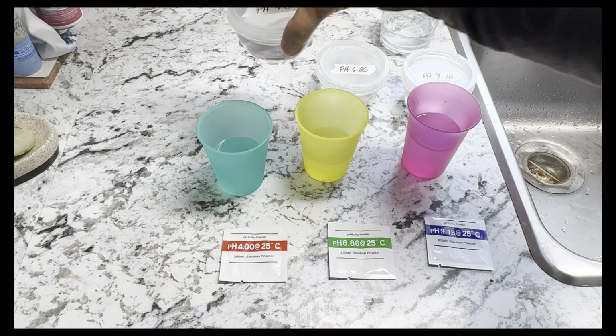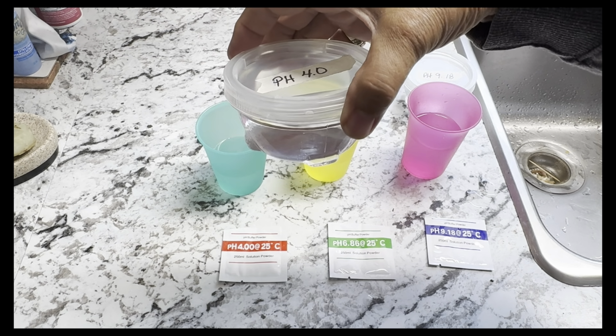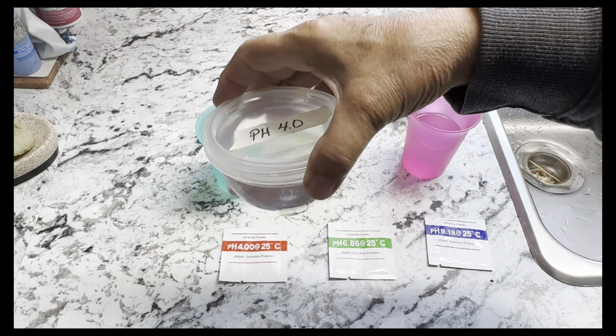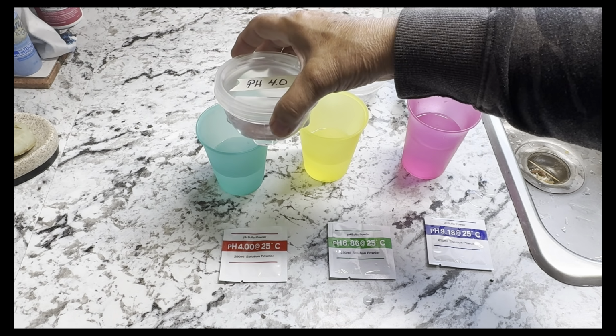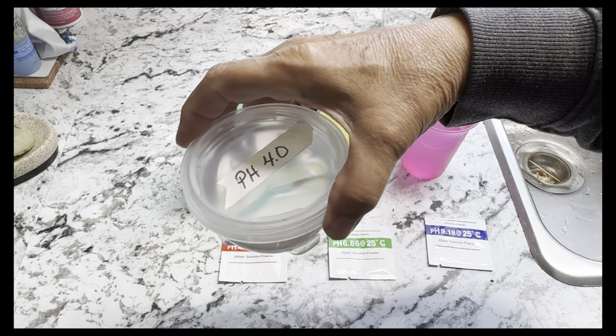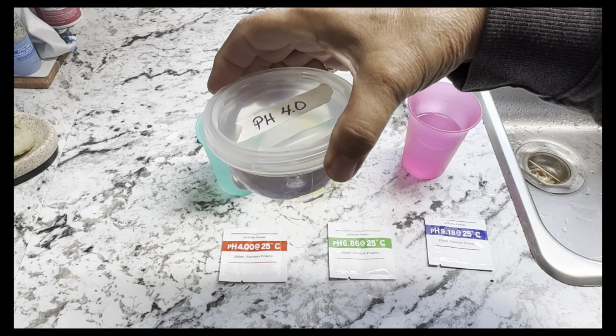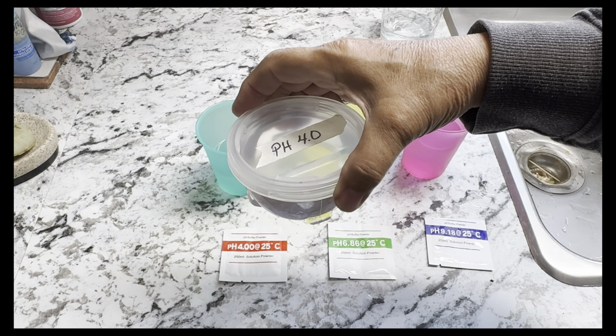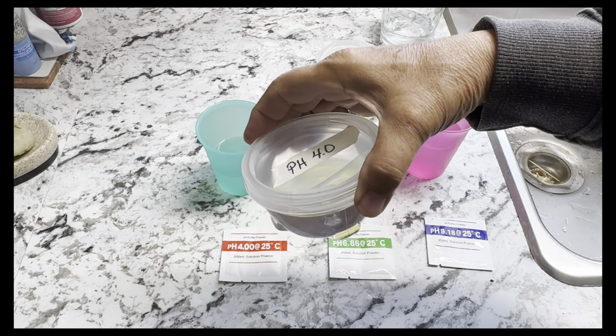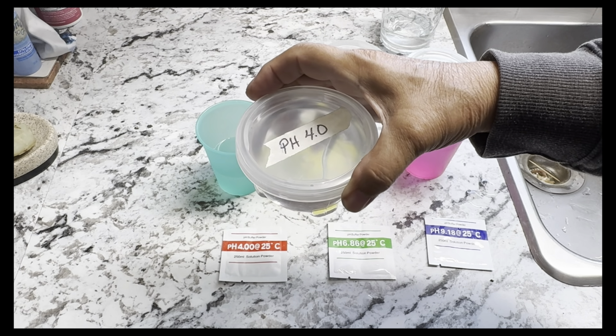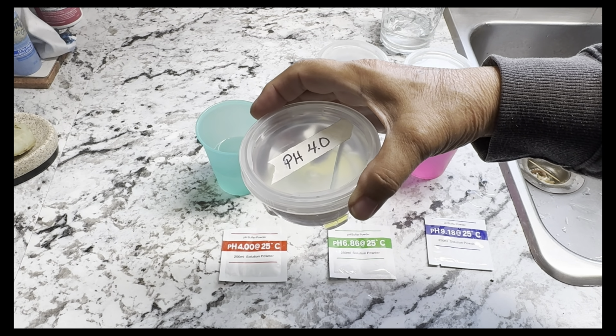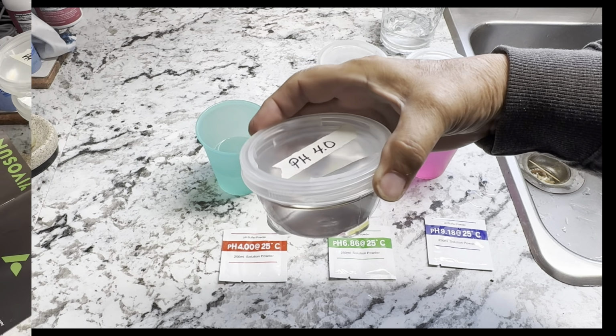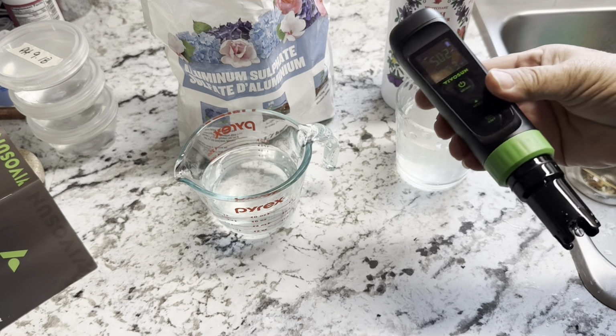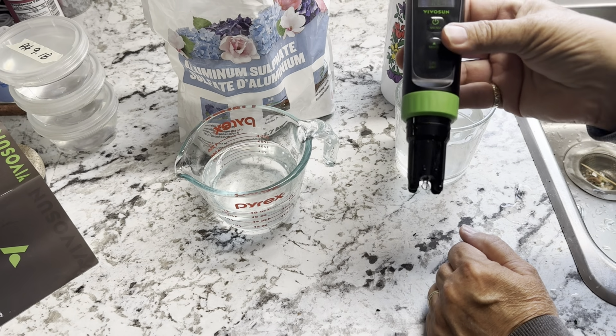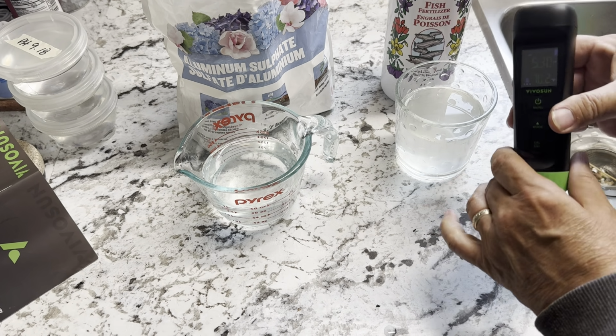So you're going to be mixing up a 250 milliliter solution from each of these packages. You don't have to use it all at once. I only put about 50 mils in this cup. You can store the excess away on the shelf out of direct sunlight. As long as it stays cool, you should be able to use this again to recalibrate over the next 3 to 6 months. So once you got your meter all calibrated, you're ready to test pH in different solutions.